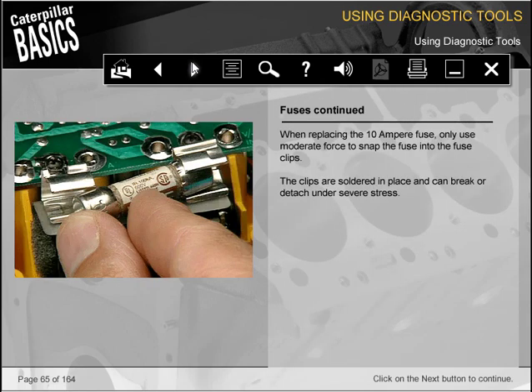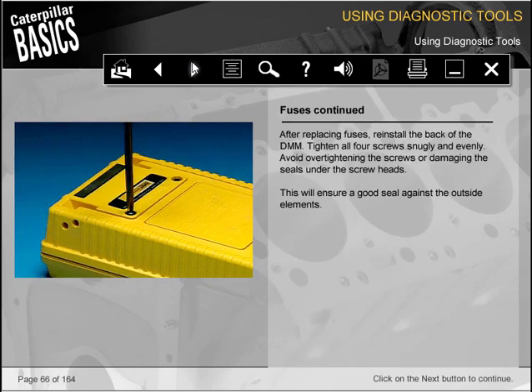When replacing the 10 ampere fuse, only use moderate force to snap the fuse into the fuse clips. The clips are soldered in place and can break or detach under severe stress. After replacing fuses, reinstall the back of the DMM. Tighten all 4 screws snugly and evenly. Avoid over-tightening the screws or damaging the seals under the screw heads. This will ensure a good seal against the outside elements.